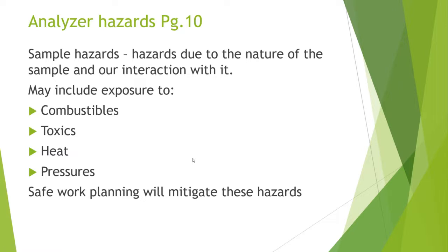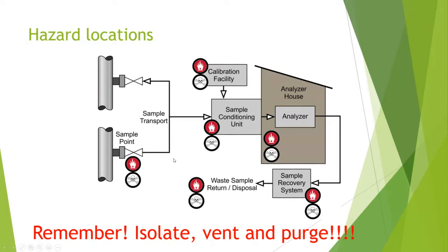If you don't know, ask — nothing is worse than an accident caused by ignorance. Hazard locations include anywhere between the pipe tap and the analyzer, including the sample point, transport system, sample conditioning unit, calibration facility, waste, and the analyzer housing itself. Wherever there's a connection, you could potentially be exposed. The golden rule is to isolate, vent, and purge. Understanding the system and how to do that is critical.